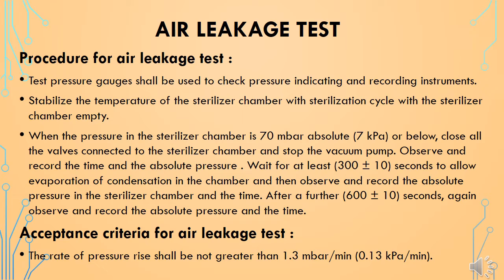After a further 600 ± 10 seconds, again observe and record the absolute pressure and time. The acceptance criteria for air leakage test: if the chamber is leaking, the pressure inside will rise. The rate of pressure rise shall be not greater than 1.3 millibar per minute or 0.13 kPa per minute.